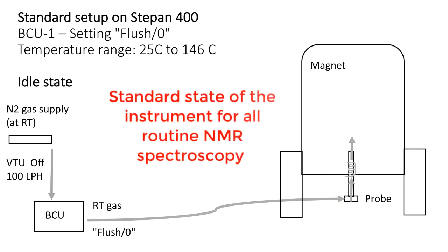This is the standard state of the NMR instrument for all routine NMR measurements. Every time you finish your variable temperature measurements, you will have to bring the instrument to this state for the next user.